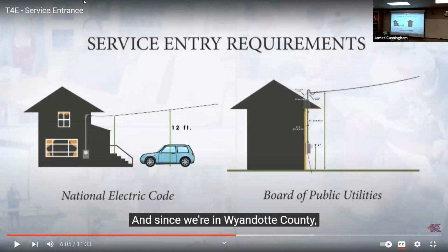Right, same here. Let me go back a little bit for this. This is a 2-story house, but the National Electrical Code says it only has to be at 12 feet to clear objects in the yard. But if we had a 2-story house here, the electrical service has to be above the upper roof, above the 2nd story. So we would have to do the same here as it's shown in here. It can't be at the lower level. It has to be up above the roof there.